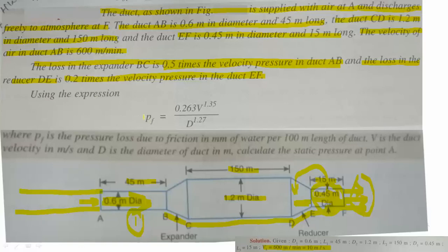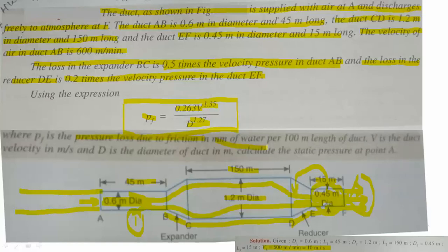Using the expression: pressure loss PF equals 0.263 × V^1.35 divided by D^1.27, we calculate frictional loss in the long pipe. Here PF is the pressure loss due to friction in millimeters of water per 100 meters length of duct.